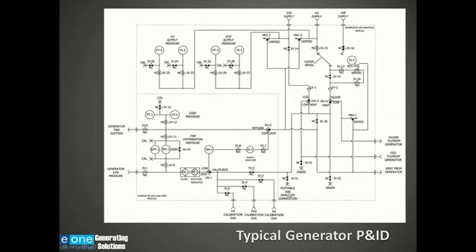You'll notice also here I've got a connection for a portable gas analyzer. Some plants will bring in a portable gas analyzer. Although this online analyzer can be used for purging, some plants like to have two analyzers online, just one to confirm the other one is operating properly.